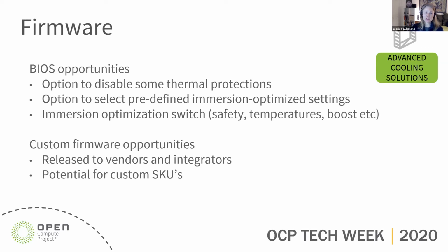So you want to make sure that they're... the request here really from the focus group is to have the opportunity of being able to have something that is potentially air cooled and immersion, right? That there's something of a switch that you'll be able to flip that will allow those temperature limits to be slightly enhanced, due to that you're dealing with a much more efficient cooling medium.